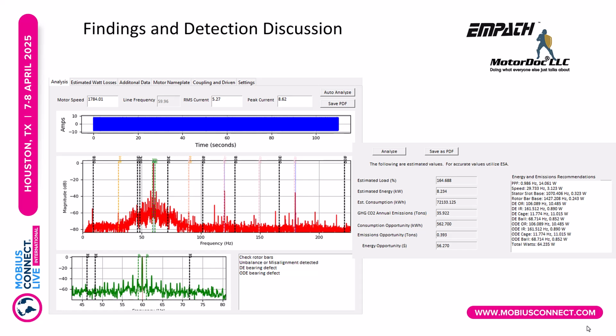This is auto-detected with most of the ESA and current signature analysis devices. It's actually extremely easy to do. We've heard people talk about how you can't detect running speed, but in fact, you can detect it more accurately than that, often down to 0.01 RPM. That becomes important because that allows us to identify conditions, including individual components of, say, a bearing. So if we take a look across this, and you see over here on the far right, now this is current signature analysis, so we're going to take some assumptions.